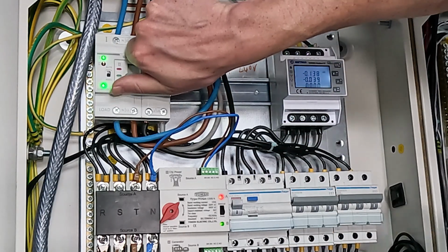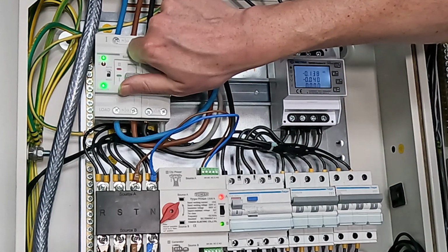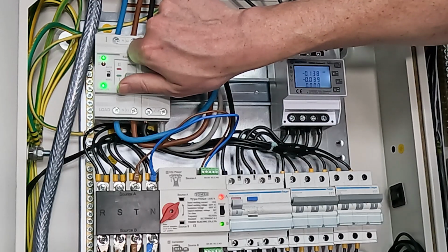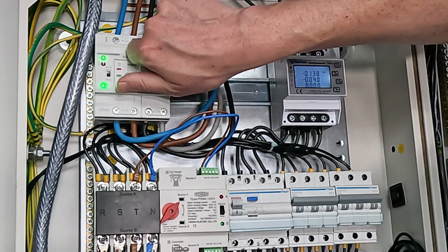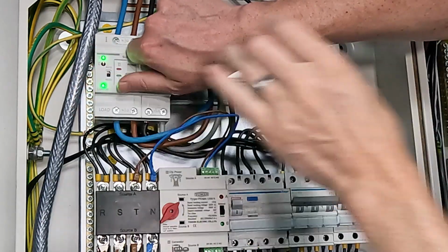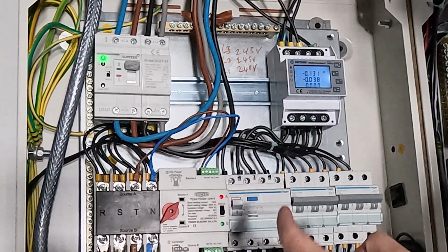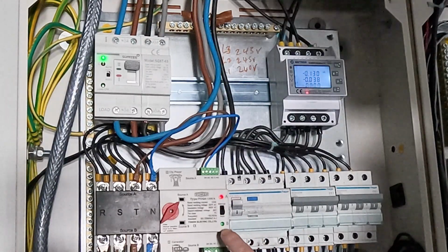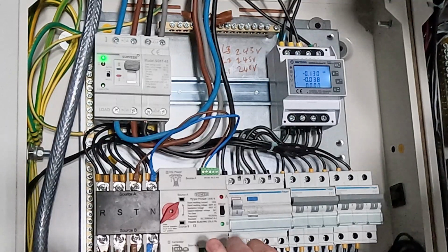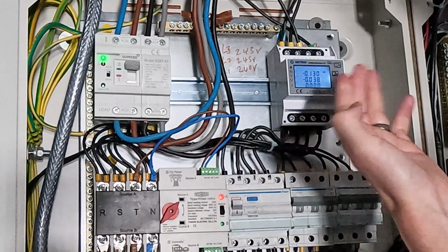So I'm going to trip the mains for the whole lab, and my lights are going to dim because the lights for the lab are on the non-critical circuits. I've got some other lights which are also on the backup, so you'll see a slight difference. Okay, there you go. And it remained on source A, and the voltage on B is non-existent. It doesn't have it, so I could touch that. And the grid is gone, but it remained on backup, and my meter remained on.